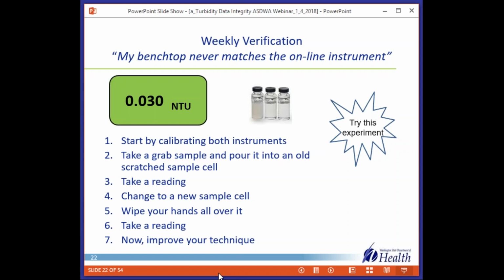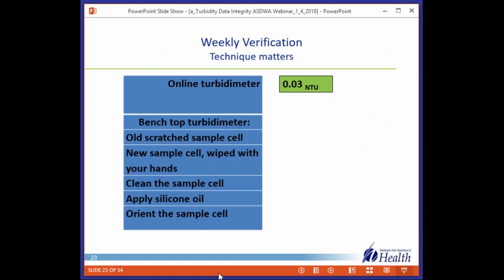So you start out with a properly calibrated online and benchtop instrument, and you take a grab sample and put it into the oldest, most scratched sample cell that you can find and take a reading. Then you change to a new sample cell and you wipe your hands all over it and take another reading. That's going to be your baseline. And now, step by step, improve your technique.